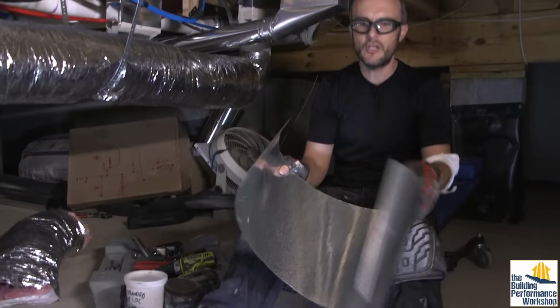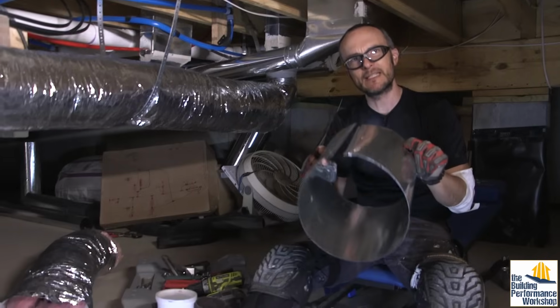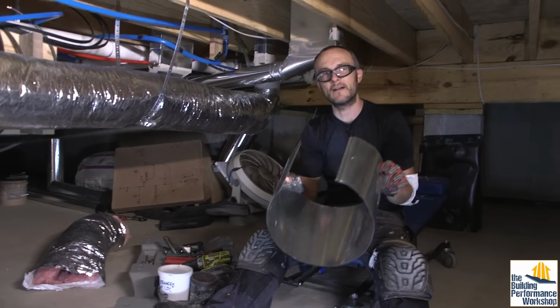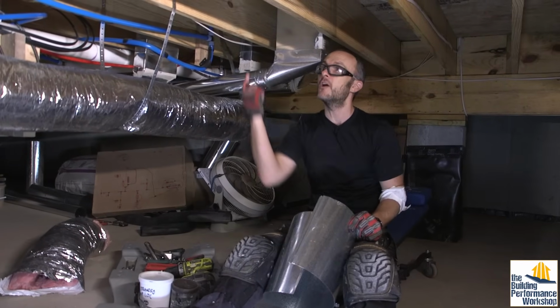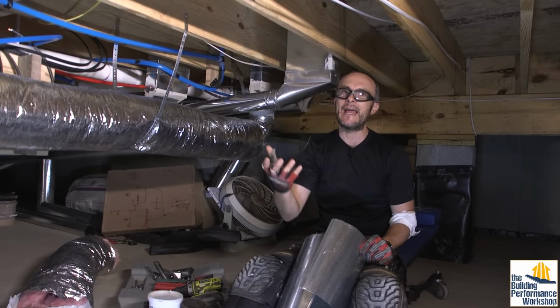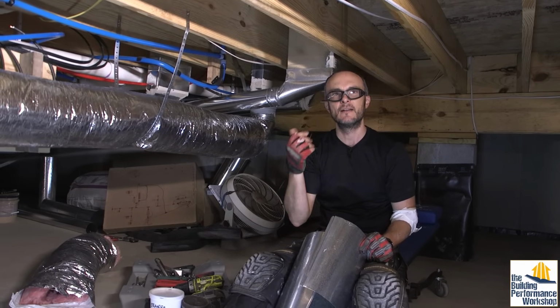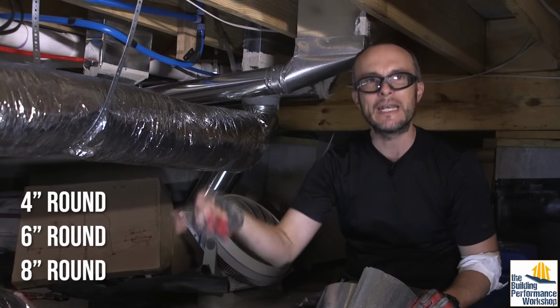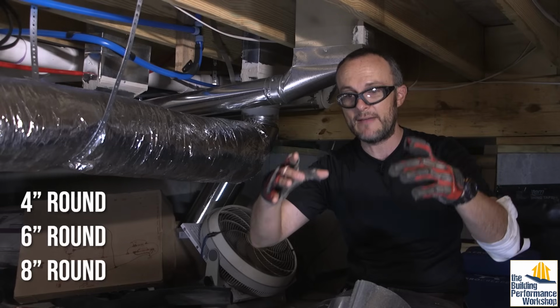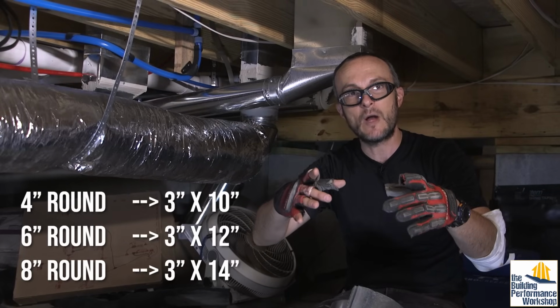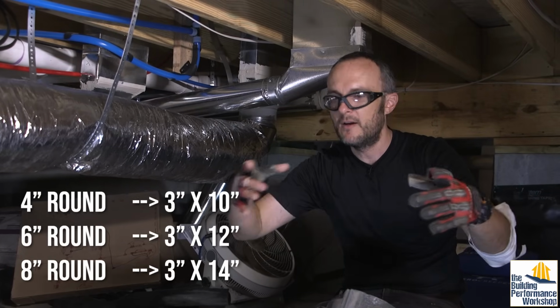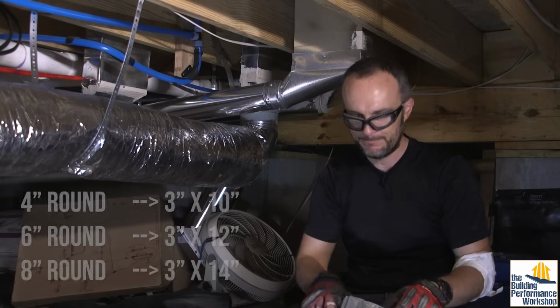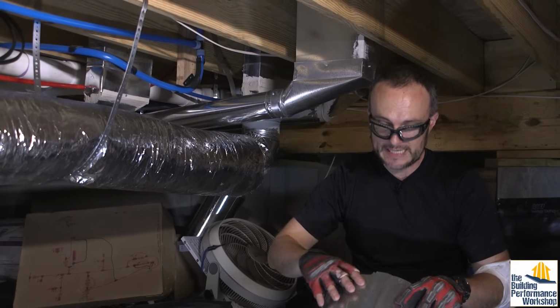With the sheet metal, mostly we're using round. Round is a little bit better at moving air than square is. But if you're going to go up into the walls, you've got to have rectangular duct. And so we're using 4-inch, 6-inch, and 8-inch going up into the wall cavities. That means it's like a 10-inch wide by the depth of the wall, or a 12-inch or a 14-inch. And this is a simple snap lock system.